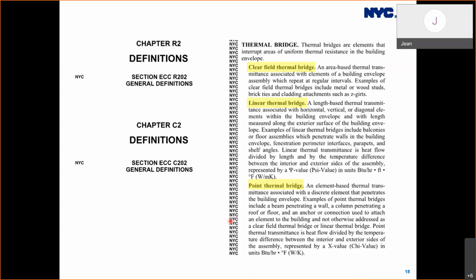And just a side note, if you look at the hard copy binder codebook of the 2020 NYCECC, you will see the sidebar NYC indicated. This normally means this is a substantial change found in the 2020 NYCECC from the 2020 New York State Energy Conservation Construction Code, 2018 IECC, and ASHRAE 90.1 2016. And like I said, the thermal bridge requirement is found only in the 2020 NYCECC and not in the model codes.